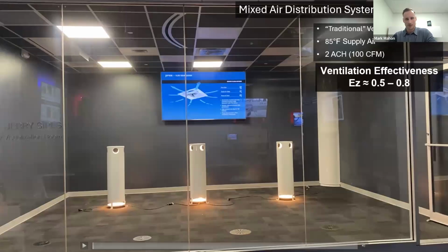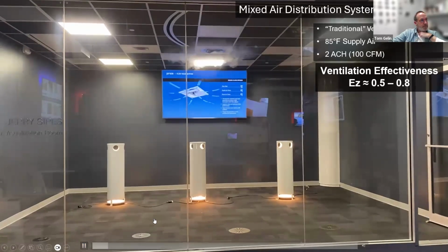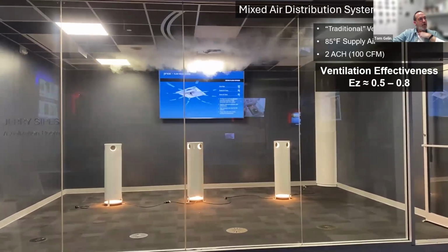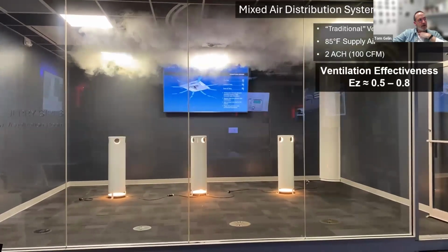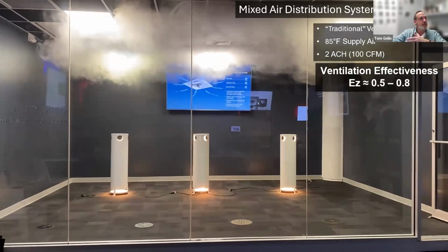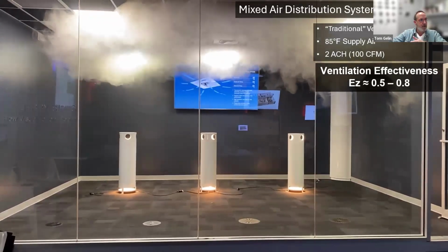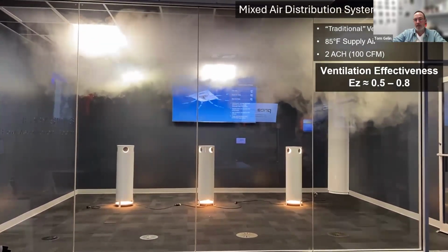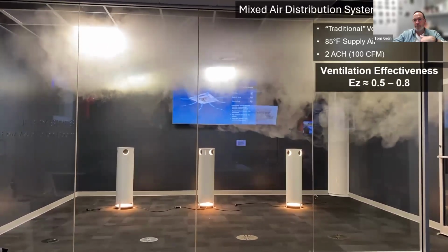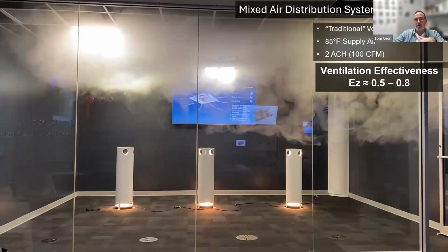Yes, sir. This is 85-degree discharge in a VAV system at 50% reduced airflow. So we just got to be careful with bumping our supply air temperature up. So we're not actually doing a whole lot of mixing here. So this is at 85. This is probably that 50% reduced airflow compared to the 200 CFM 8-inch diffuser. 100 throws not really there. We get a little bit of dropping and mixing. So if we elevate the temperature up to 95, we're going to be stratifying significantly more. So that's just the one point where we're saying, hey, let's sweet spot. 85 is the real sweet spot. You have to really solve your BTU calc. But let's do it maybe with higher airflow diffuser, not higher temperature out of the box.